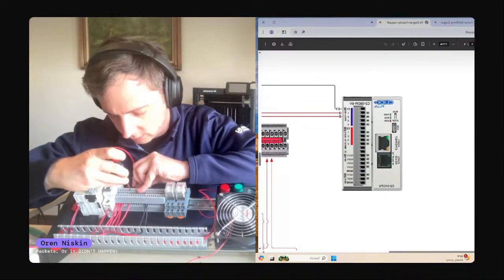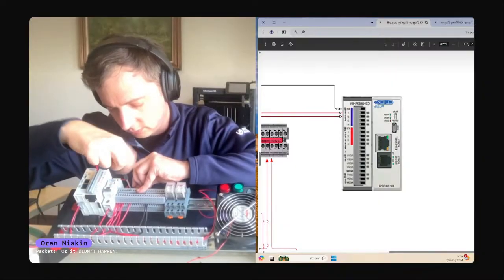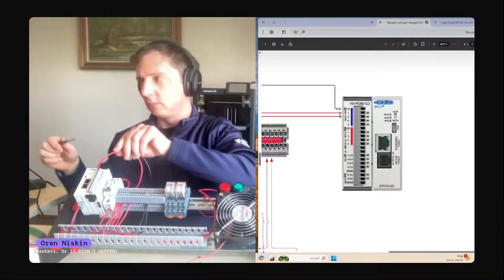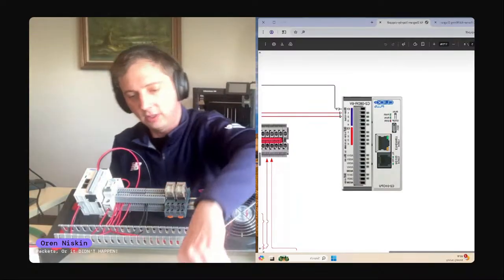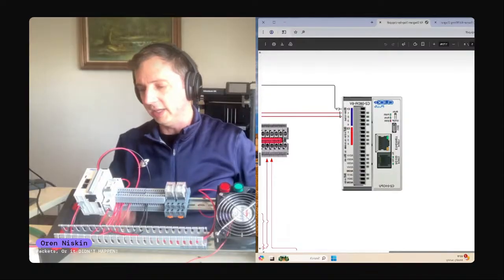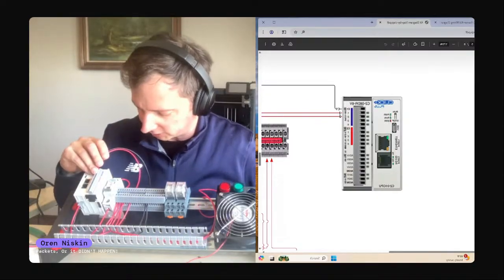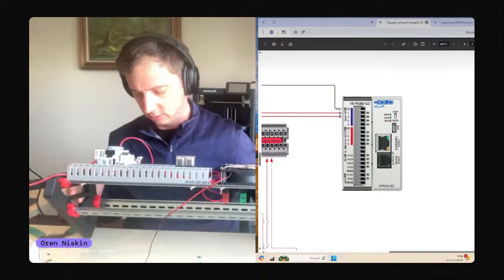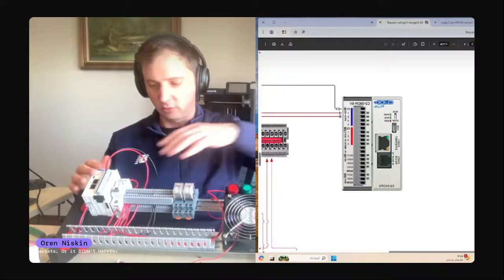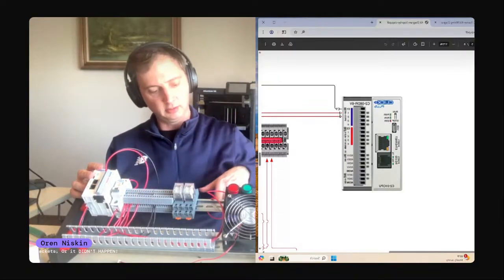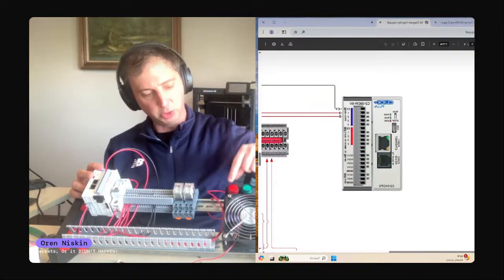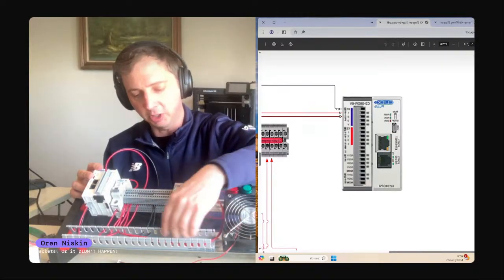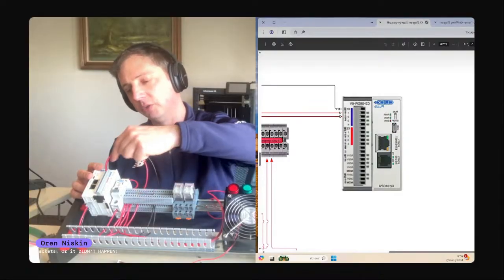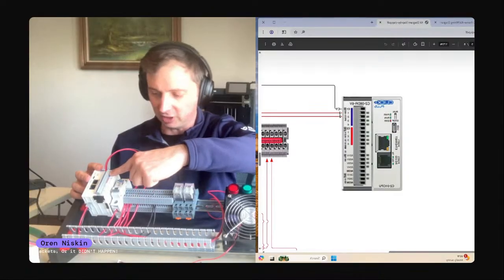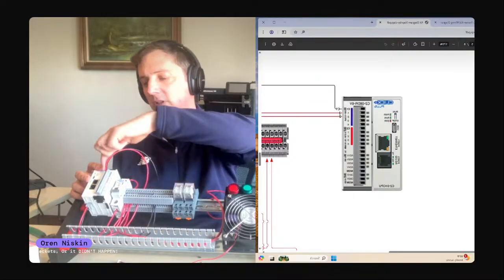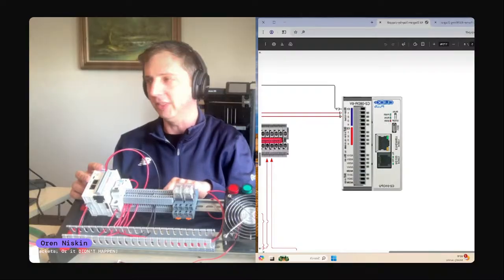Okay, so that is the button. We have it going from the power to the top of the button, out of the bottom of the button. When you push the button, it makes and breaks that circuit, out of the bottom of the button, and then over to this terminal block where it goes into the PLC as the first input, digital input, and then the power comes back out here to the negative. And that is our circuit.